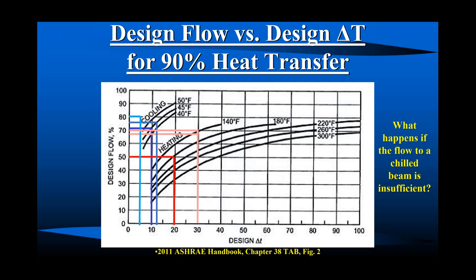Well, usually instead of balancing the entire system, the quick fix that is thought to be the solution is to what? Here's the issue, it's 58 degrees, it should be cooler. And that temperature is turned down. And our fabulous sensible only cooling system turns into a latent load removal system. And things go badly. So chilled beams is an emerging system, fabulous system, comfortable system, healthy system, but without the right balancing, can go very badly.